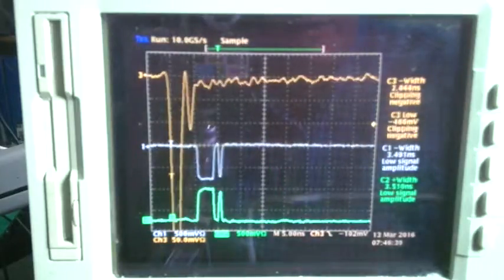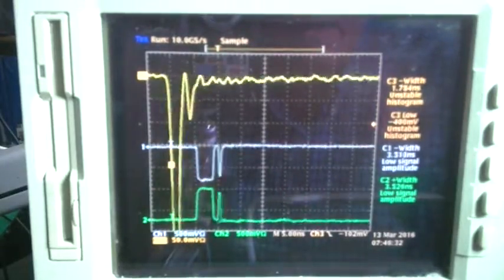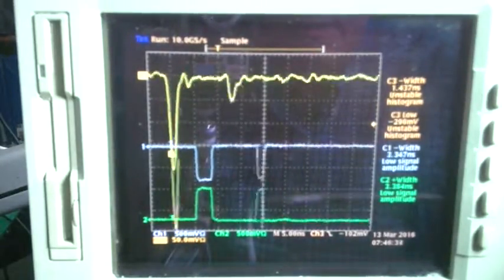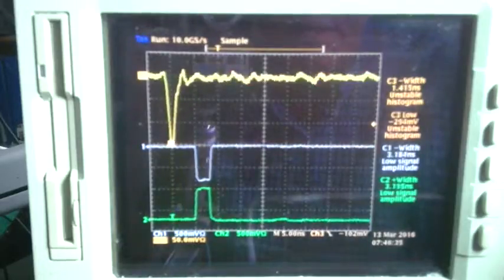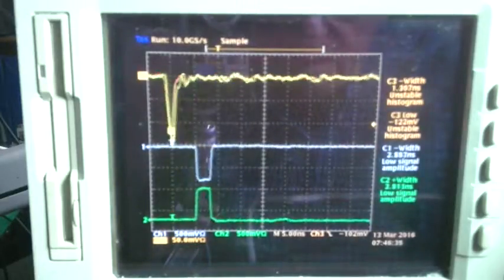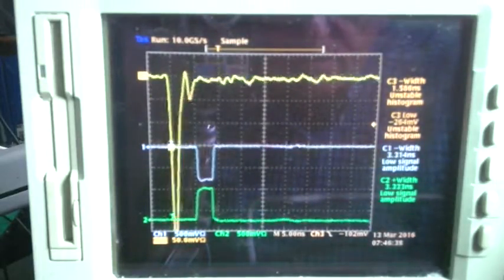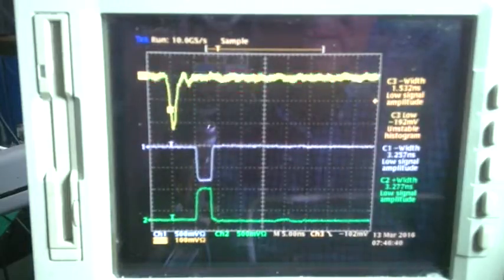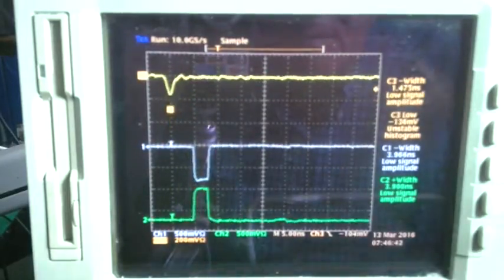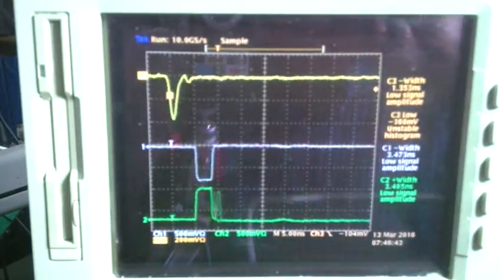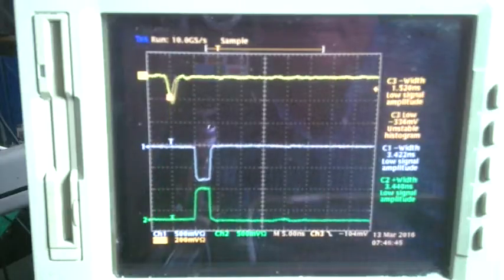Let me change the gain of trace 3, which is the photomultiplier output, from 50 millivolts to 200 millivolts. The trigger level is still the same.